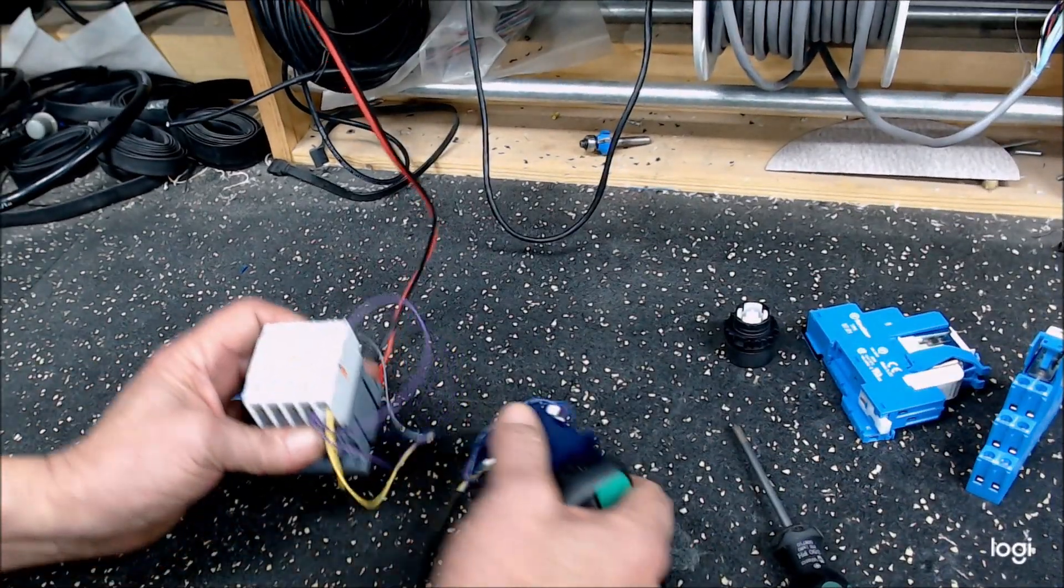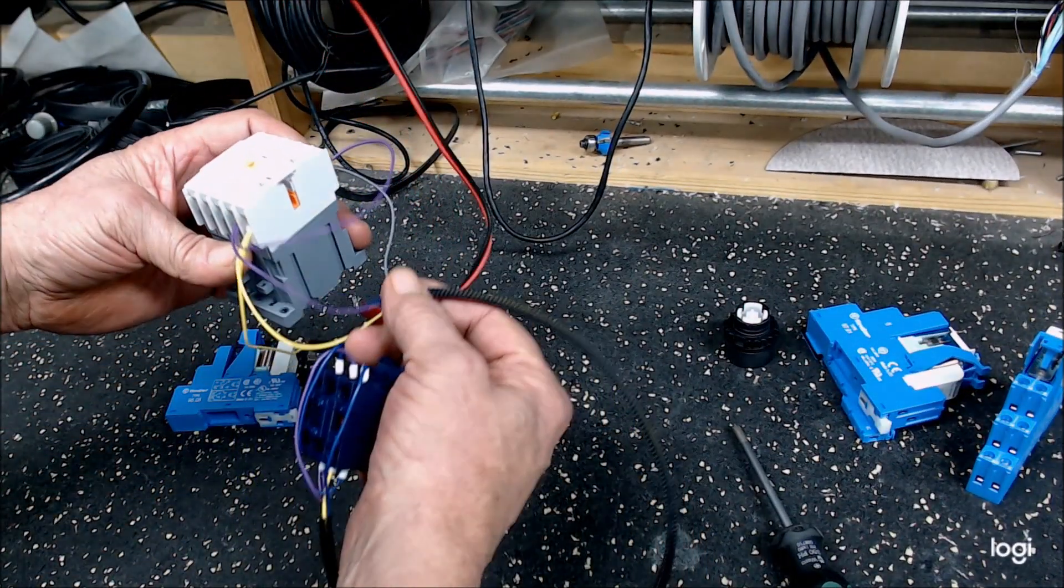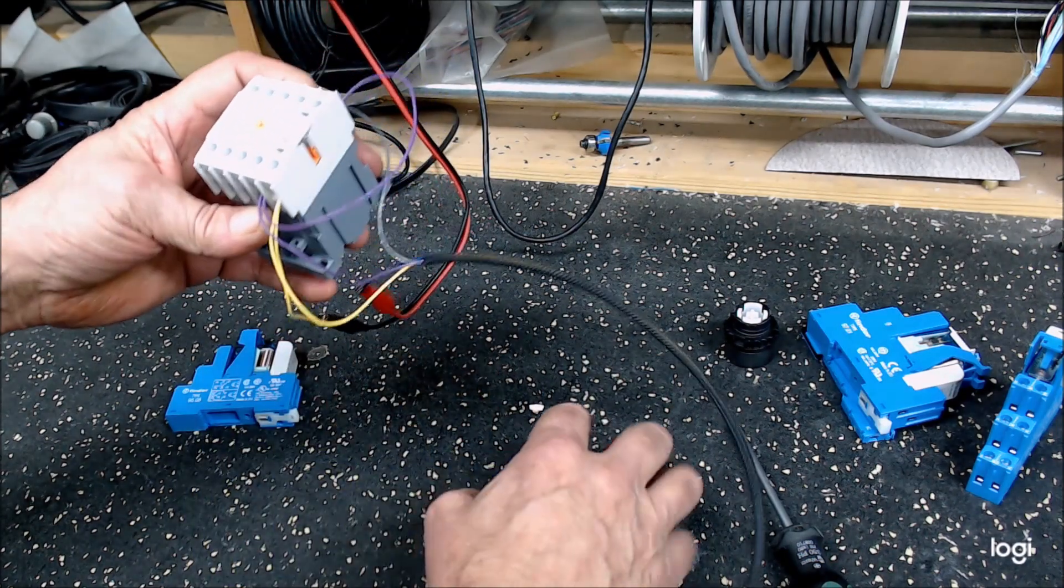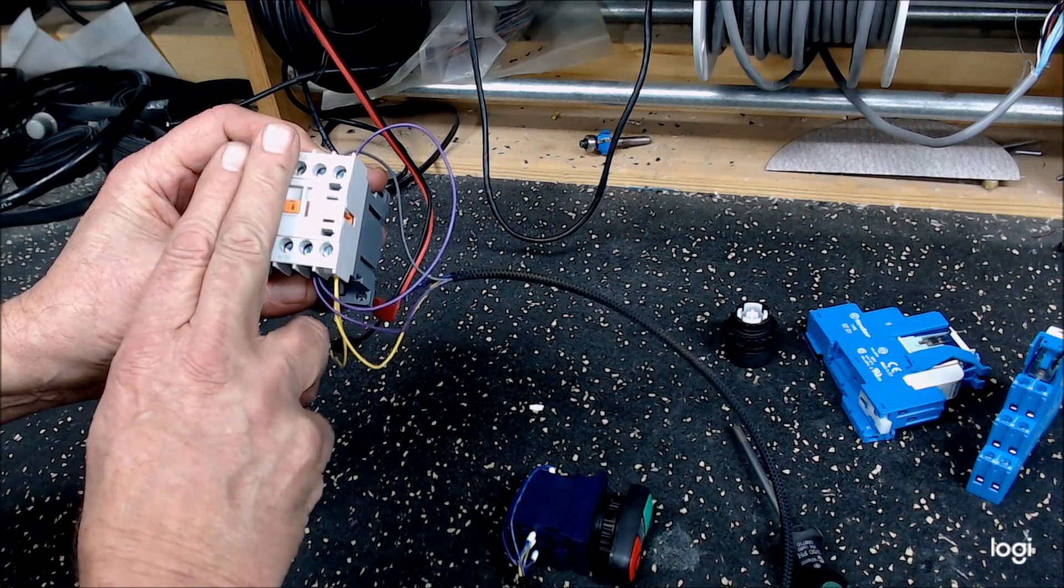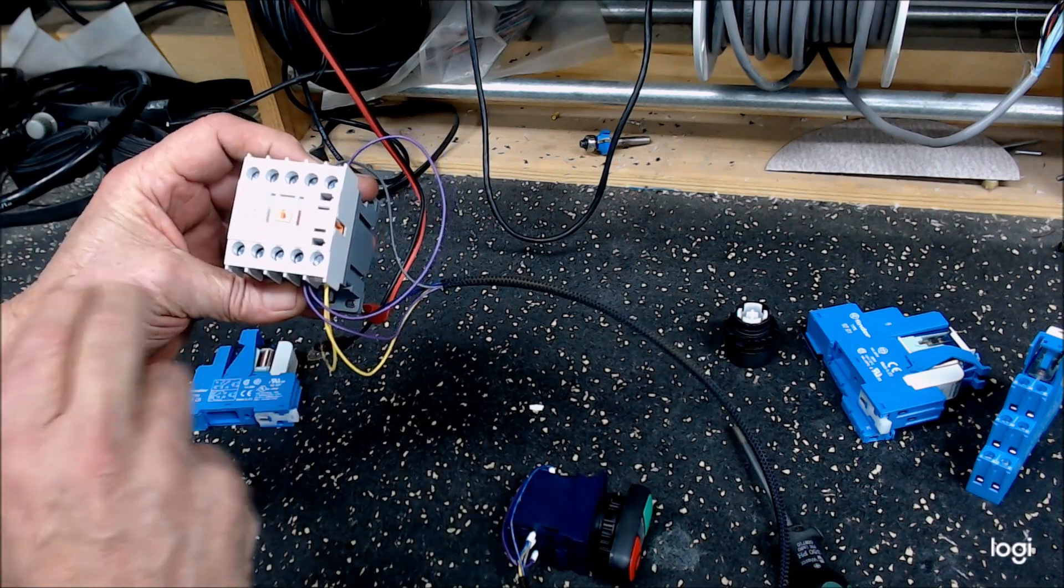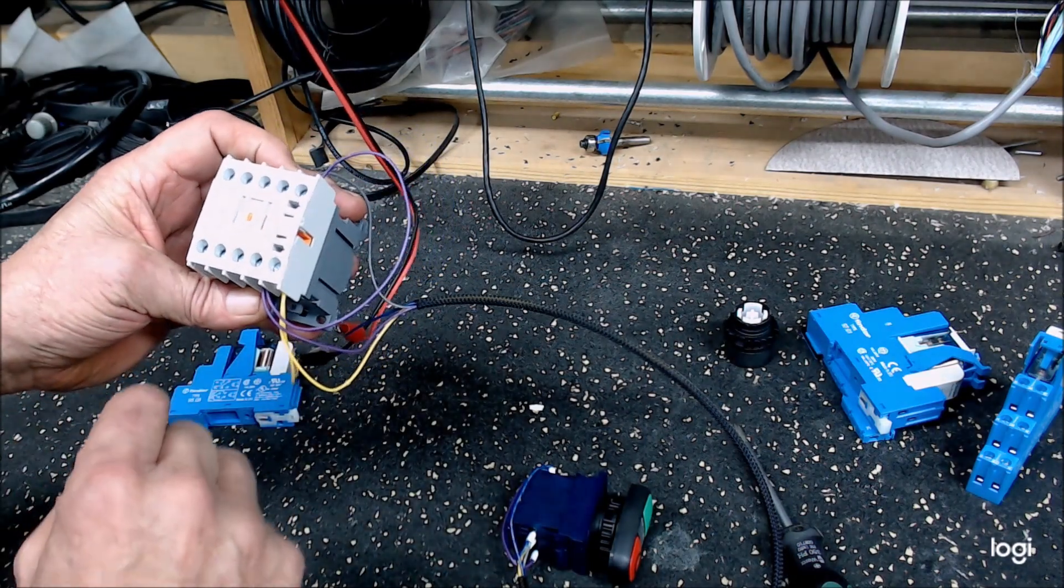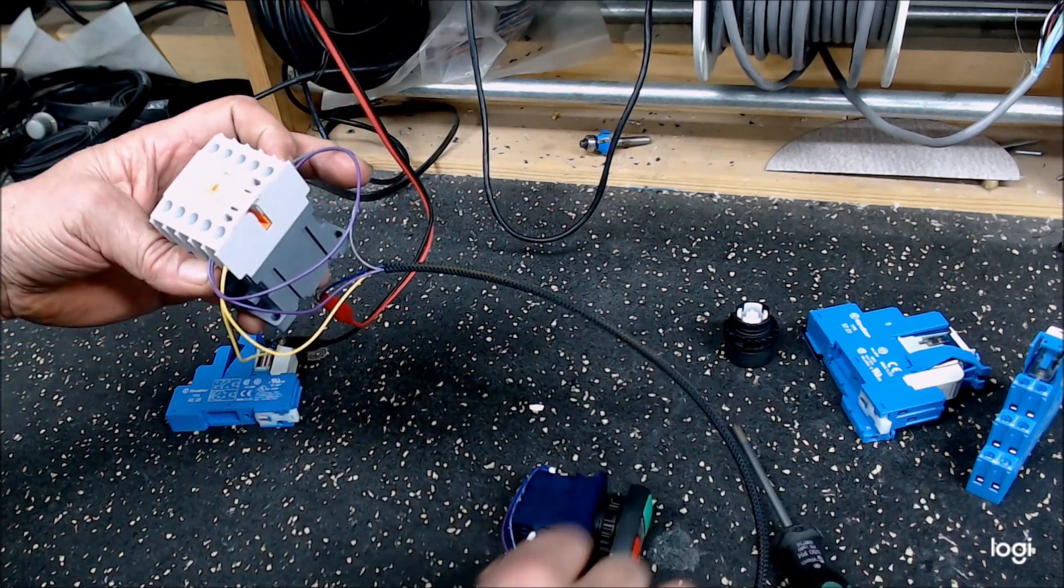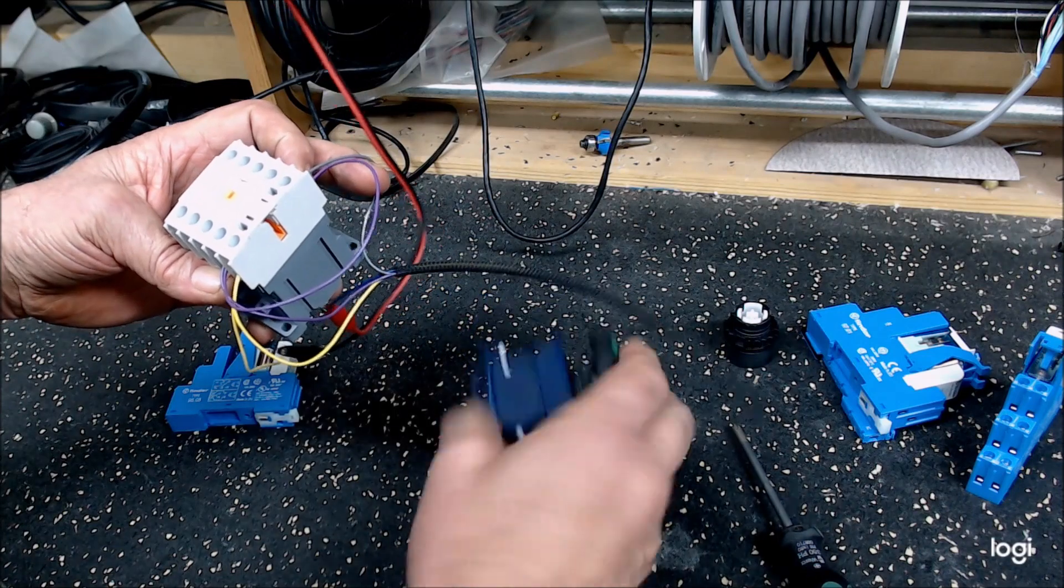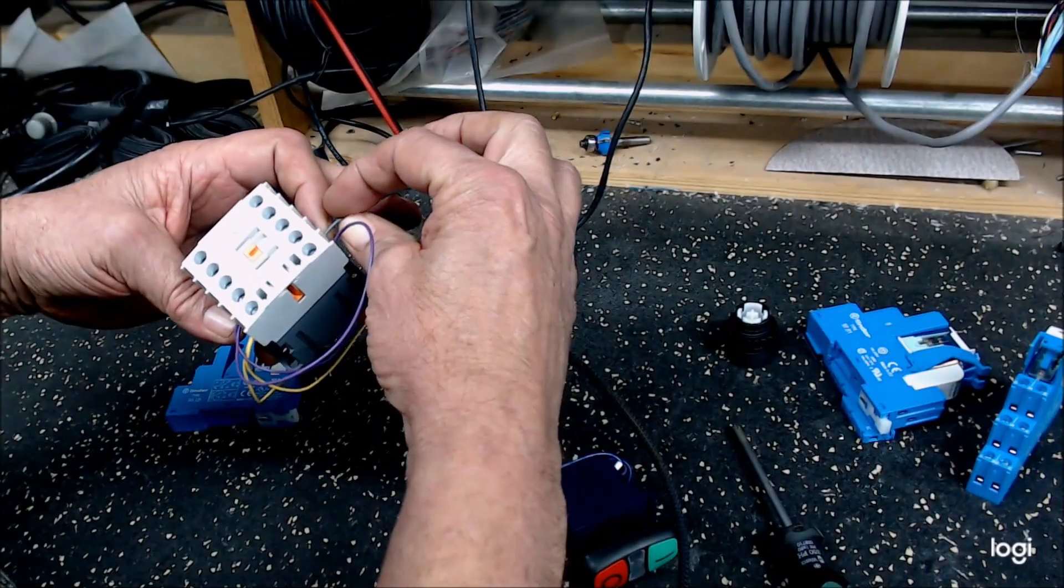So the contactor - again, this could be used for high voltage, higher draws. This actually isn't a very large contactor, but nonetheless it'll show what's going on. My 24 volt power that comes through the normally closed switch goes to the common of the normally open. When that contact is closed, it energizes the coil.